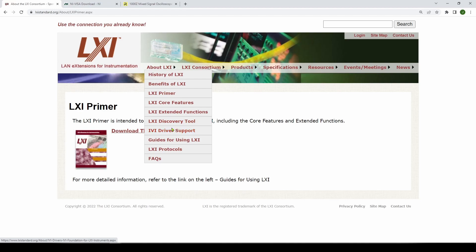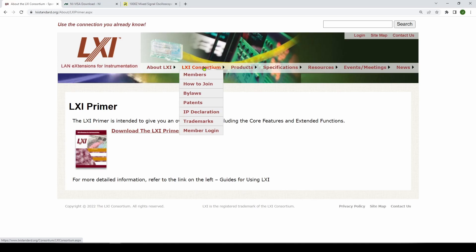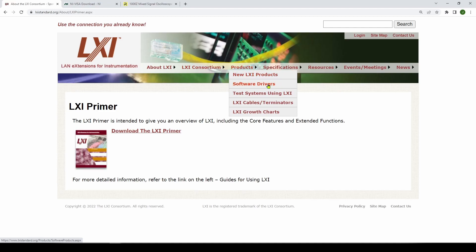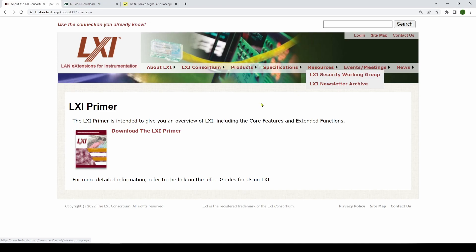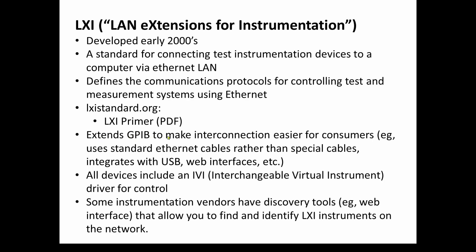There's a consortium — a group of people getting together that develops these standards. You're going to have drivers that drive the equipment using these LXI specifications. I encourage you to take a look — it's a really good way to understand. LXI basically extends GPIB to make interconnection easier for consumers. For example, it uses standard Ethernet cables rather than special GPIB/IEEE 488 cables, integrates with USB, has web interfaces where you can fire up a web page and find LXI devices on the network. All devices in this LXI standard include what's called an IVI driver, which we're going to use in the future to drive our devices.